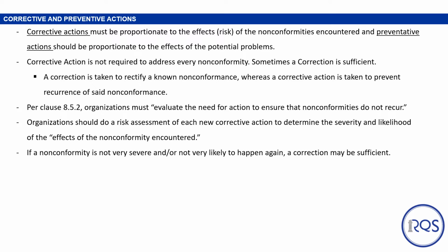Per Clause 8.5.2, organizations must evaluate the need for an action to ensure that nonconformities do not recur. The phrase evaluate need implies that there is not always a need. Organizations should do a risk assessment of each new corrective action to determine the severity and likelihood of the effects of the nonconformity encountered. If a nonconformity is not very severe and/or not likely to happen again, a correction may be sufficient.